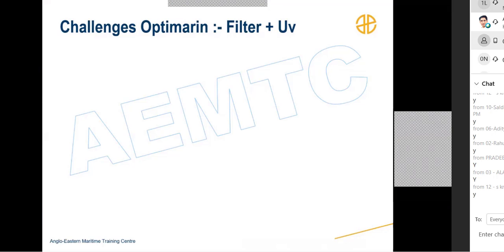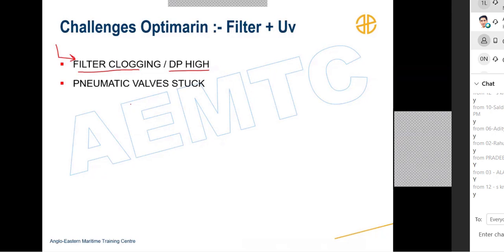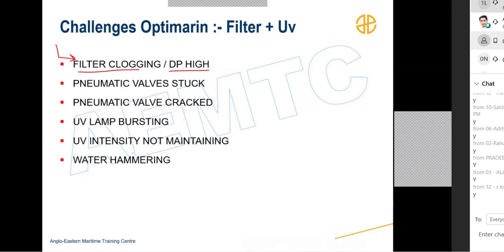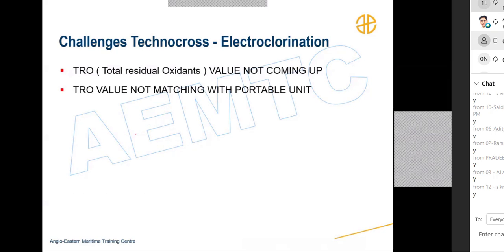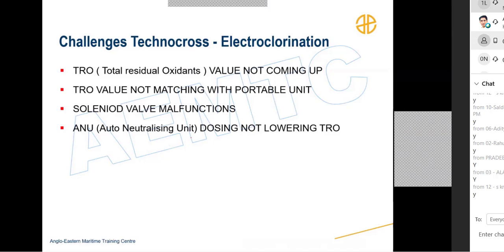Challenges can be many, so let's go one by one. Filter clogging. These are written down based on the feedback from candidates like you. So some people face high DP, frequent clogging of filters, valve getting stuck, valve crack, UV lamp bursting, intensity not proper, water hammering, stripping related issues, sampling issues, TRO value not coming up, TRO values not matching with the portable units, solenoid valve malfunctions, ANU auto dosing not lowering the TRO. So yes, problems can be many, guys. Now it depends on a case to case basis how you're going to deal with the situation.